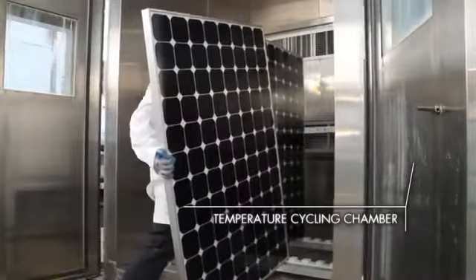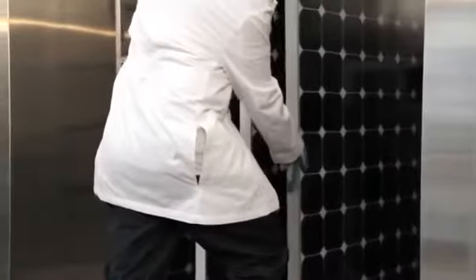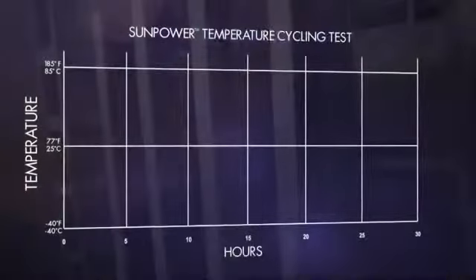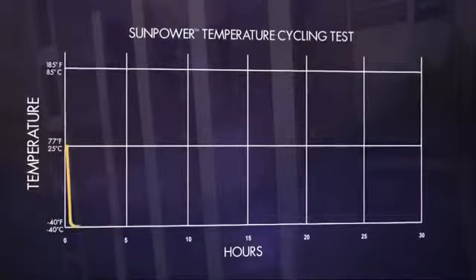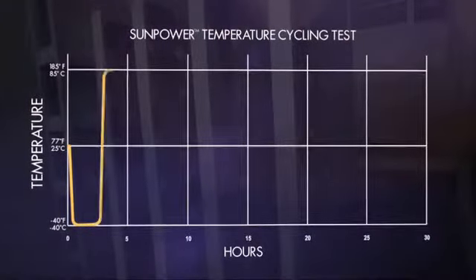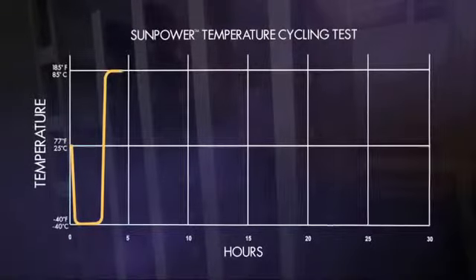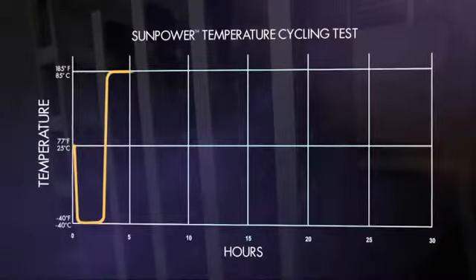This is the temperature cycling chamber, designed to simulate real-world temperature changes for over two and a half decades. Inside, solar panels are subjected to rapidly changing temperatures. First, the temperature falls to negative 40 degrees Fahrenheit. Then it rises to 185 degrees Fahrenheit. All in under five hours.